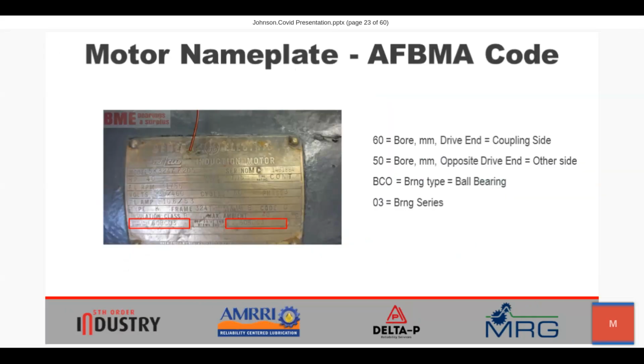So I'm going to run you through some logic that we can find, starting with the nameplate information for the motor and the use of a simple radial calculator that's available for you to right size your grease feed practices, with the expectation that you're likely to find a substantial amount of time savings available through these means. If you go to your motor nameplate, you will find details that look like we see here. And we see in the red boxes 60 BCO3 and 50 BCO3.